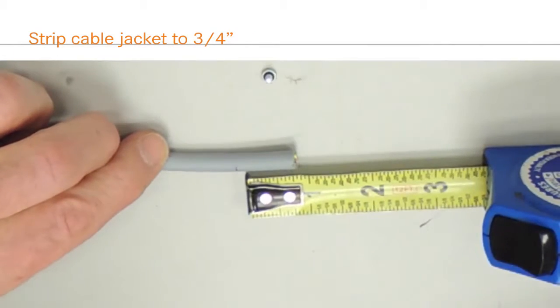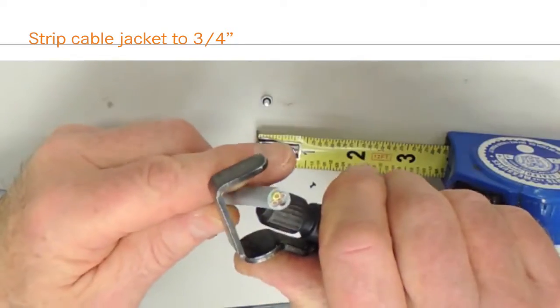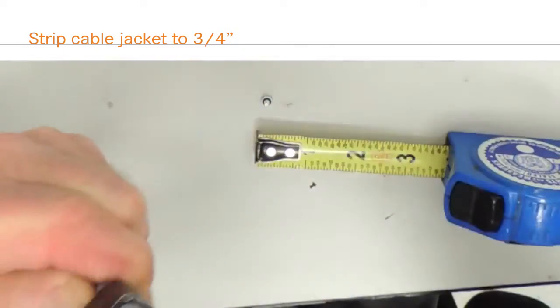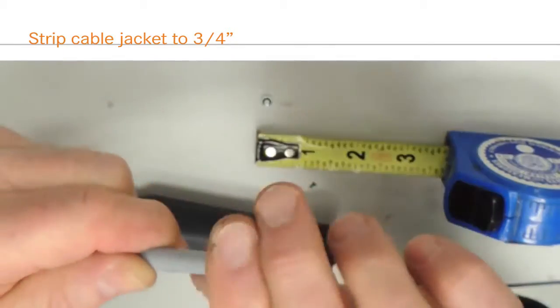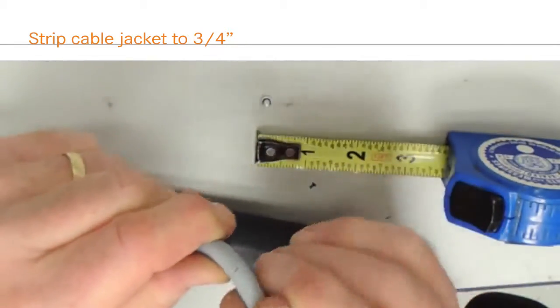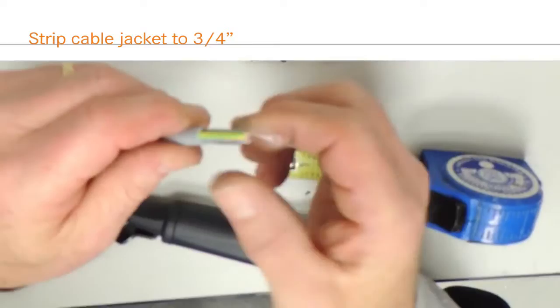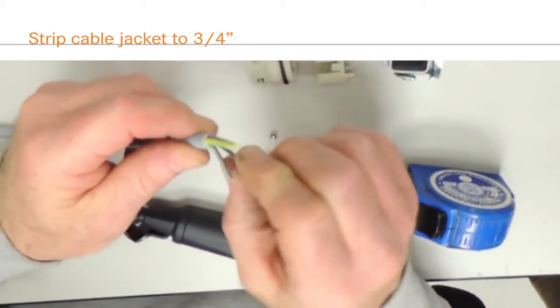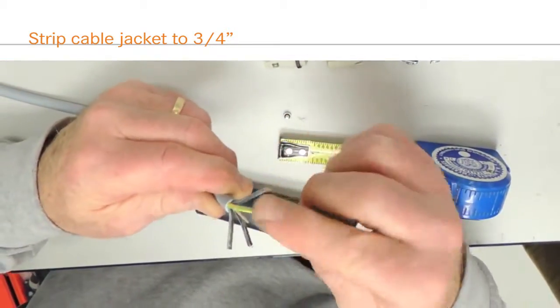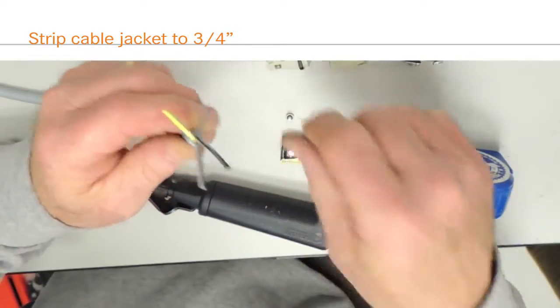First, prepare the cable by stripping the outer jacket to the appropriate length. The jacket should be stripped back enough to allow you to easily terminate the individual conductors, but not so much that the jacket is stripped past the hood's gland when assembled. For EPIC HA3 housing, three-fourths of an inch is sufficient stripping length.